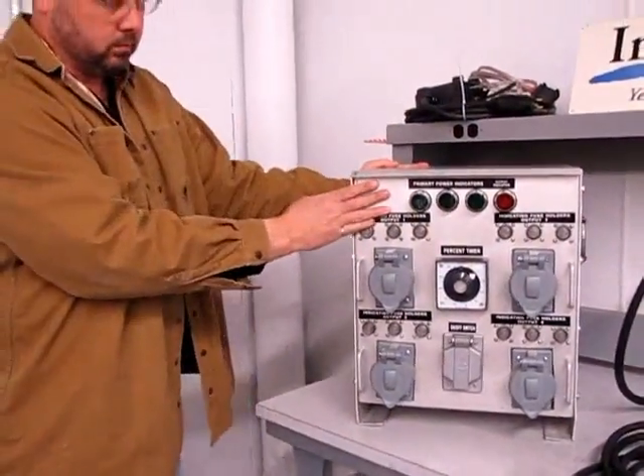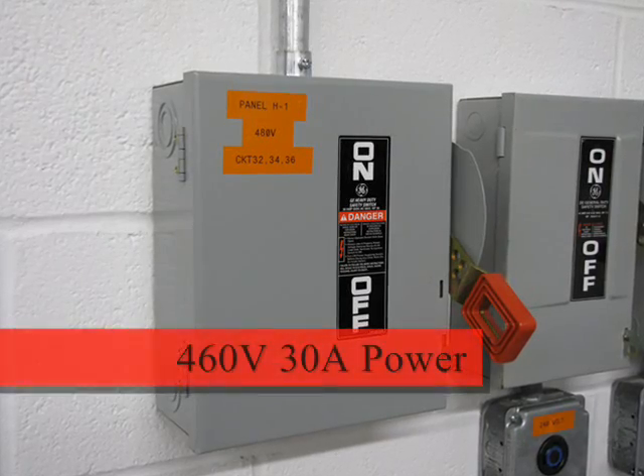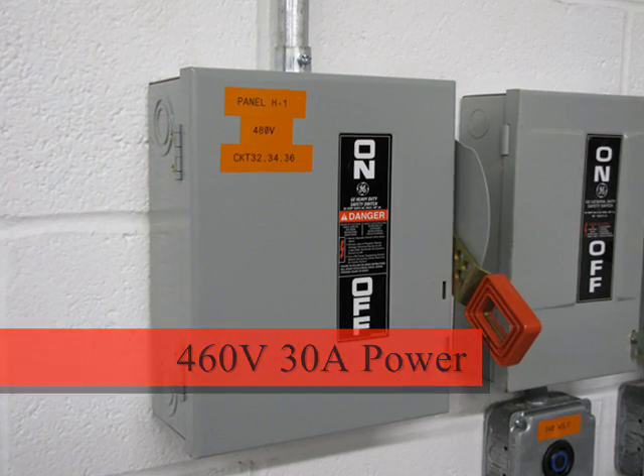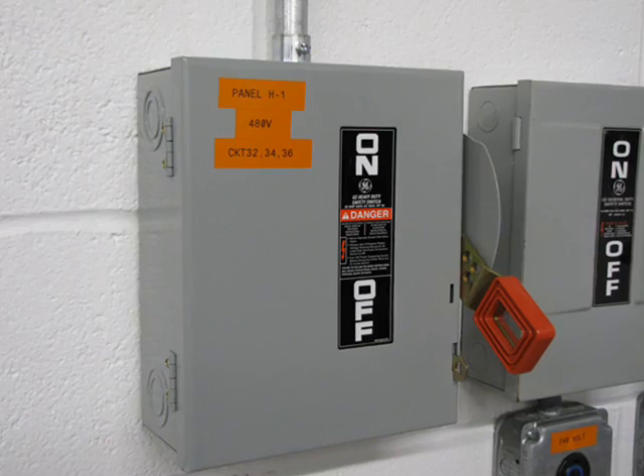Have a licensed electrician wire the control panel to a properly rated 460 volt fused switch panel. When moving the control panel, be sure the power is off. Do not plug the power streamer into the control panel yet.